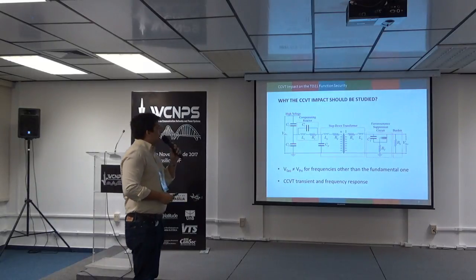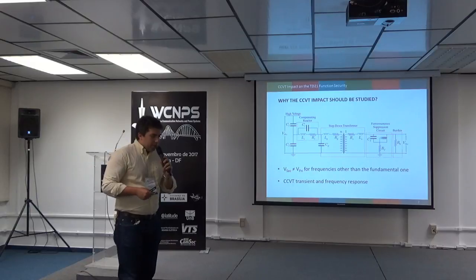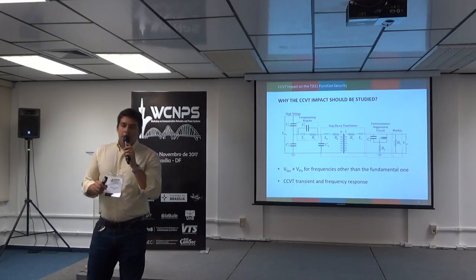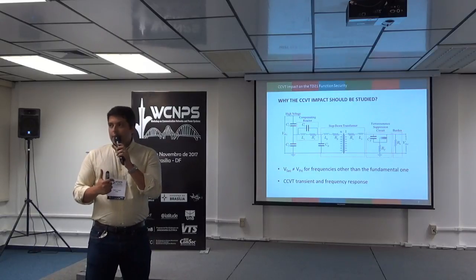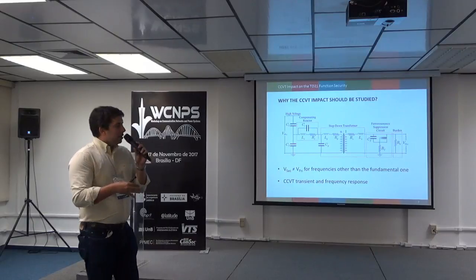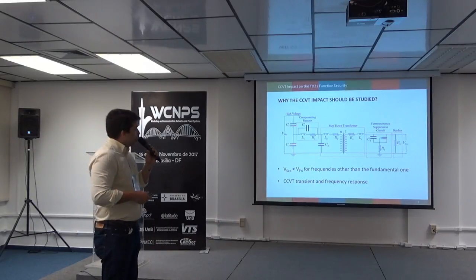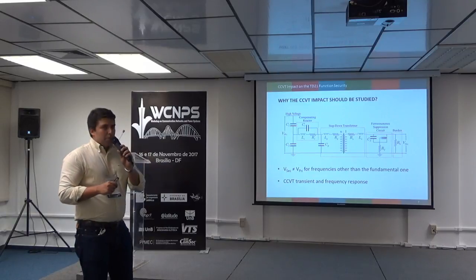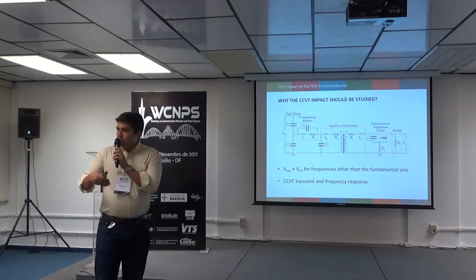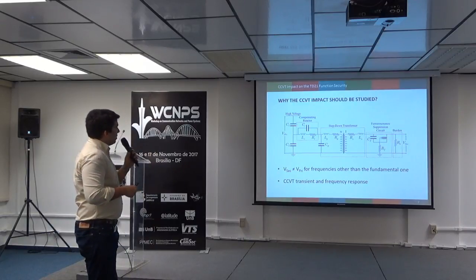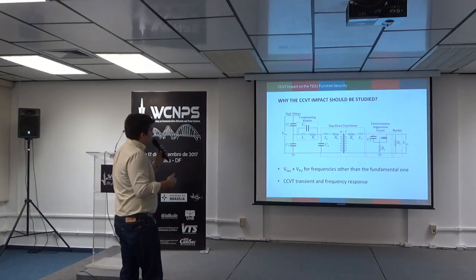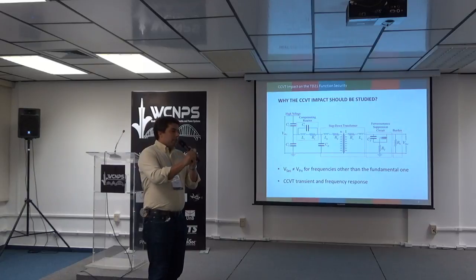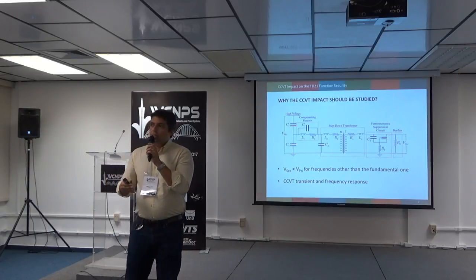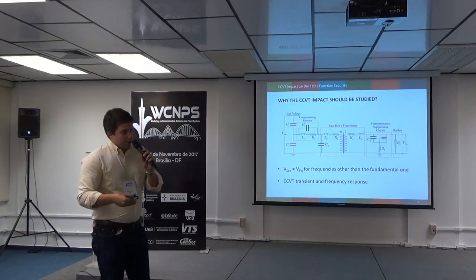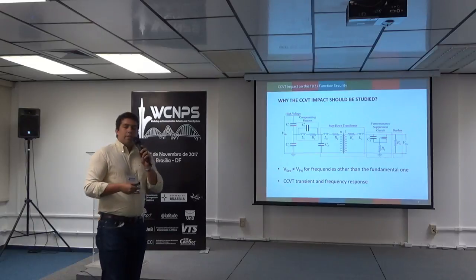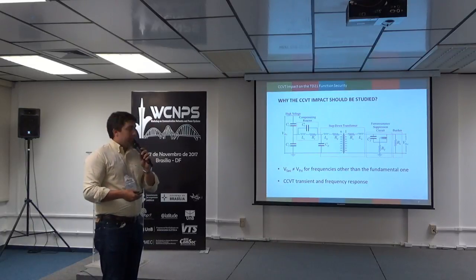Well, why do we have to understand the impact of the CCVT on this function? Even when we are using phasor-based techniques, the CCVT transient response may affect the traditional phasor-based protection functions. But now, in this recent trend in time domain protection functions, this effect may be even more of a cause for concern for us, because we can attenuate some transients, and we can add some phase displacements to the signal. So we have to analyze if this function is secure, if this function will operate when it has to operate, or if it will restrain when it has to restrain.